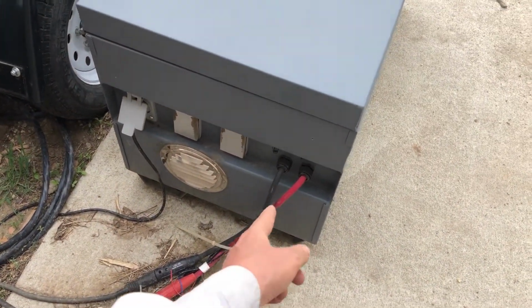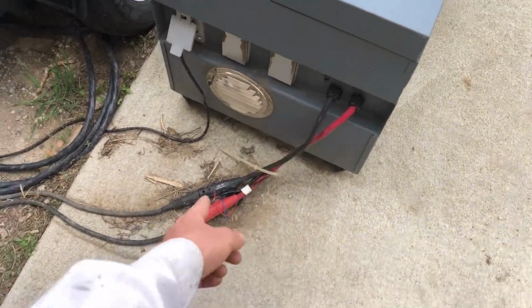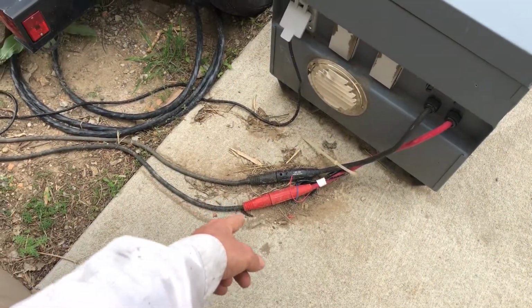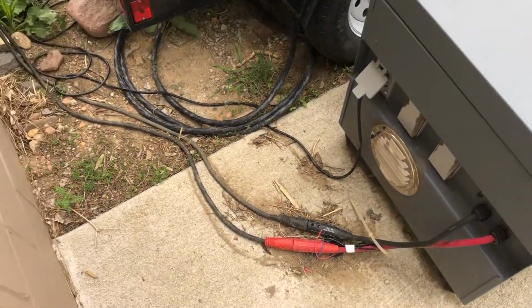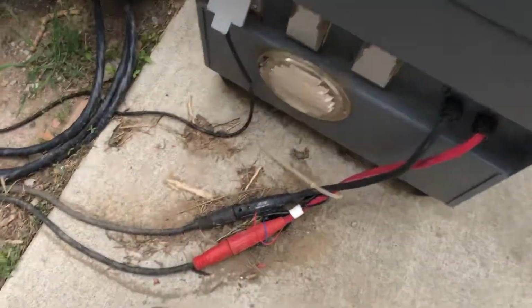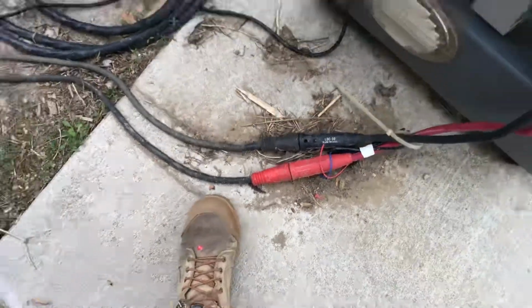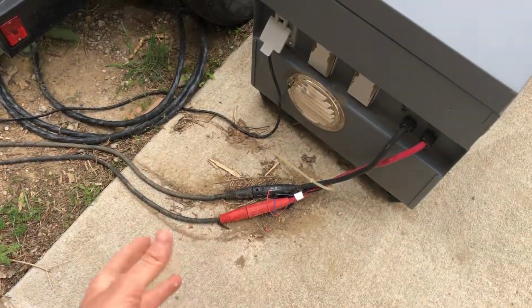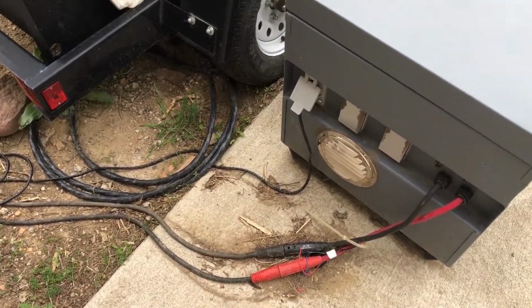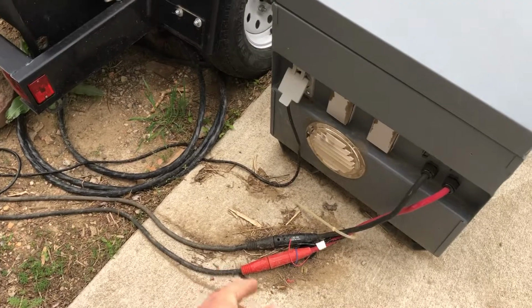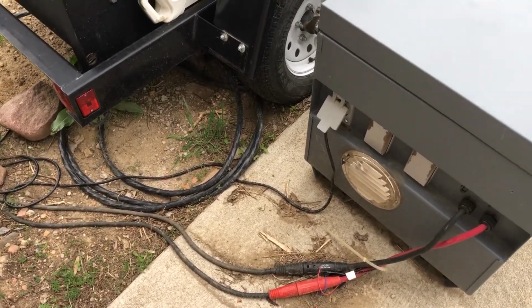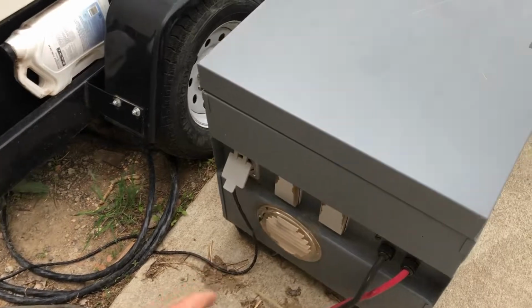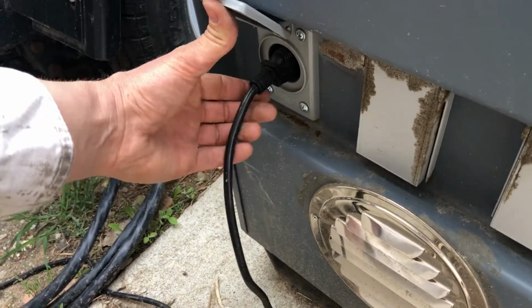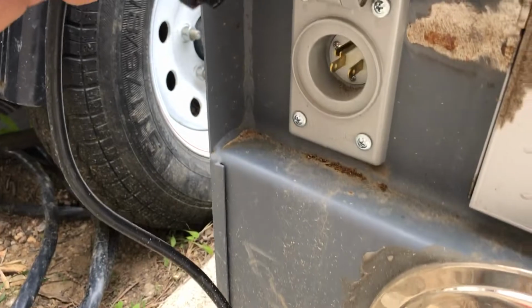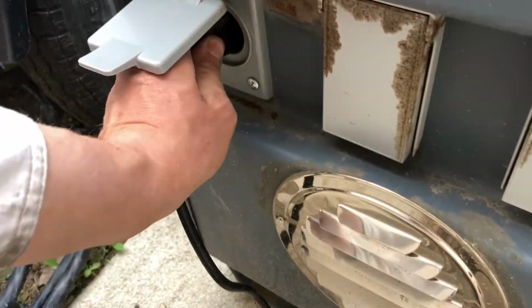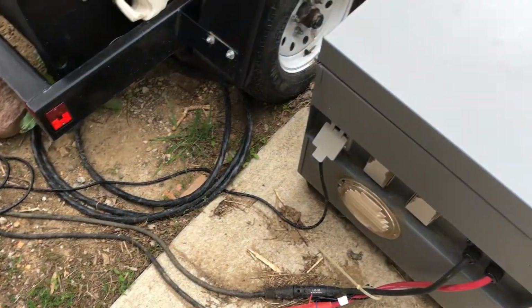This connection here is 2x0 to these connectors, and then it's 2 gauge thereafter. I intended to upsize this to 2x0, but it turns out the way the charger I have on the system is working, the loads are about 50 amps less on these cables than I had originally calculated for. And then this is an inlet, so it goes the opposite direction of a regular outlet, and this is how we feed the power in for charging the battery.